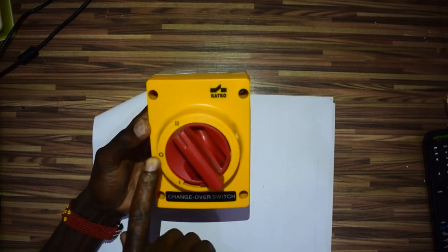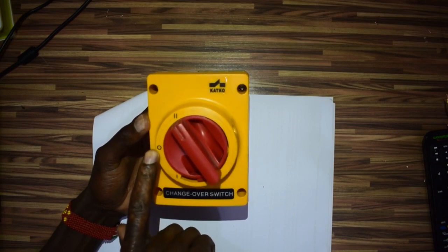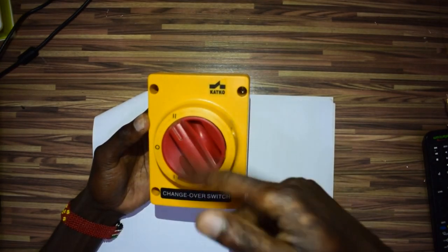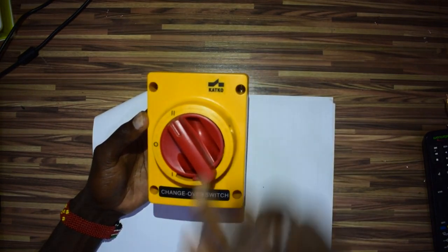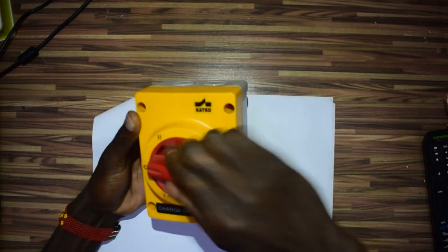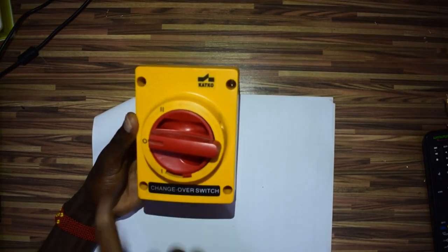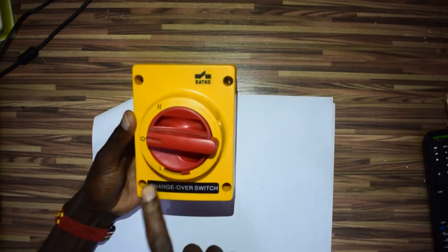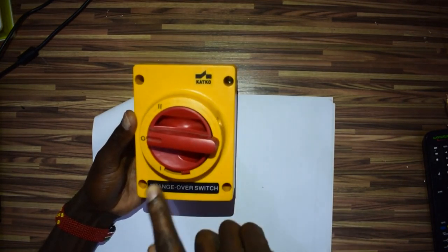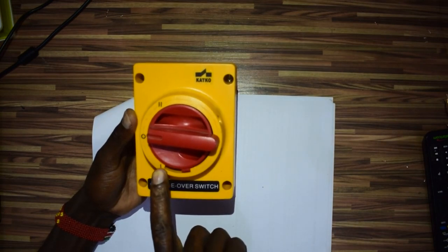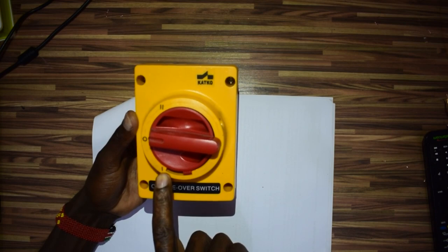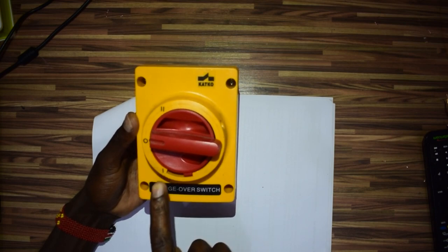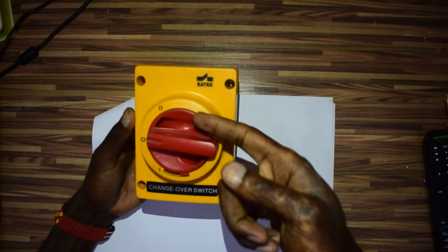It has a zero position, which means it's not connected to either side of the power. Then we have positions two and one. You can choose to connect your main power source from the utility company to one, and your backup power from a generator to number two.